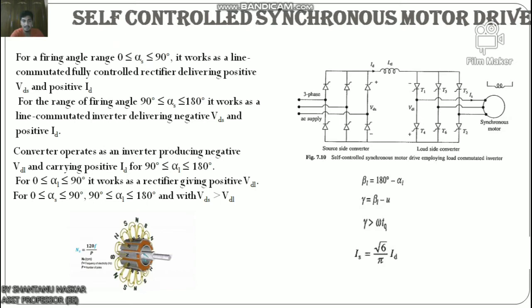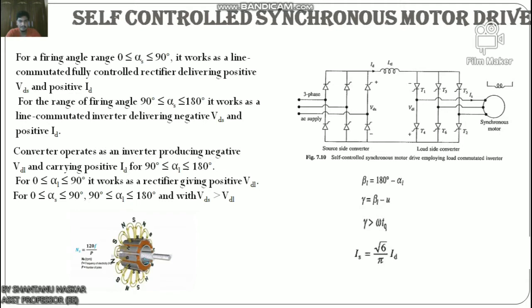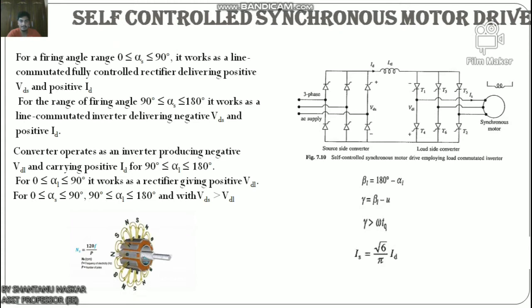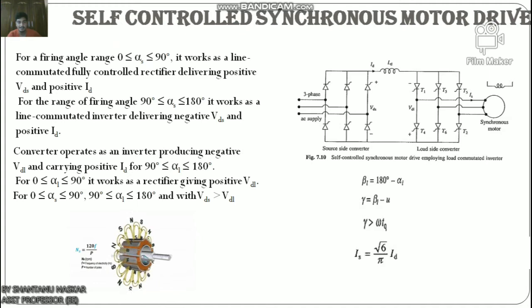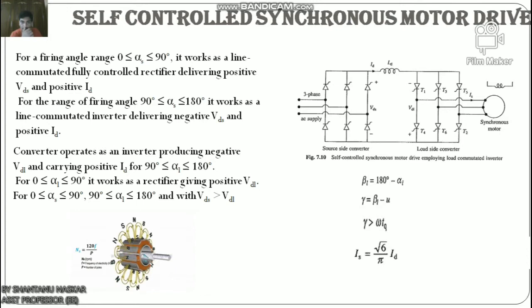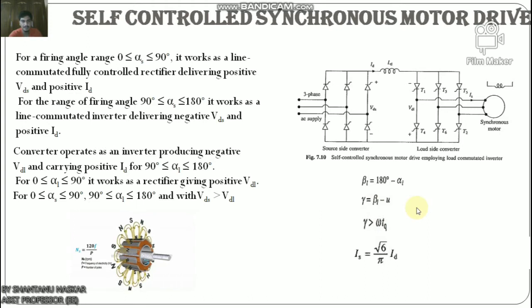The damper winding does not play its conventional roles of starting the machine as an induction motor and damping oscillations, because rotor and rotating field speeds are always the same. In a simple control scheme, the drive is operated at a fixed commutation lead angle βlc for the load-side converter working as an inverter, with β1 = 180° − α1 and α1 = 0°. When good power factor is required to minimize converter rating, the load-side converter working as an inverter is operated with constant margin angle control.